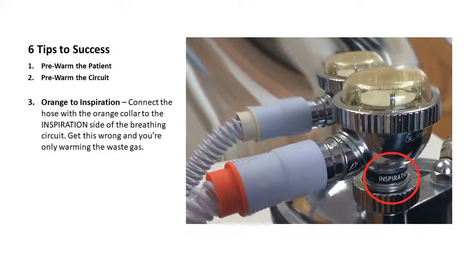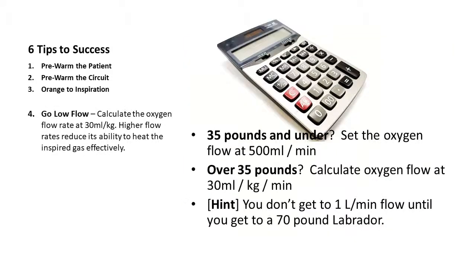Tip number 3, orange to inspiration. Connect the hose with the orange collar to the inspiration side of the breathing circuit. Get this wrong and you'll only be warming the waste gas. Tip number 4, go low flow. Calculate the oxygen flow rate at 30 mL per kilo. Higher flow rates reduce the circuit's ability to heat the inspired gas effectively.